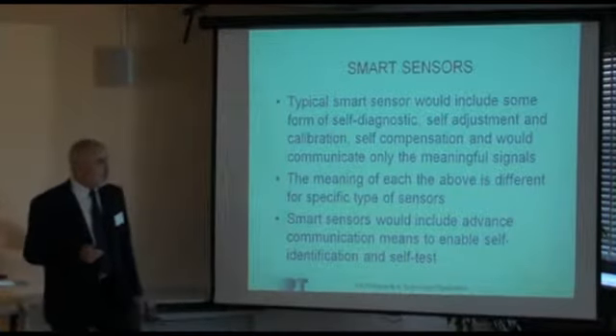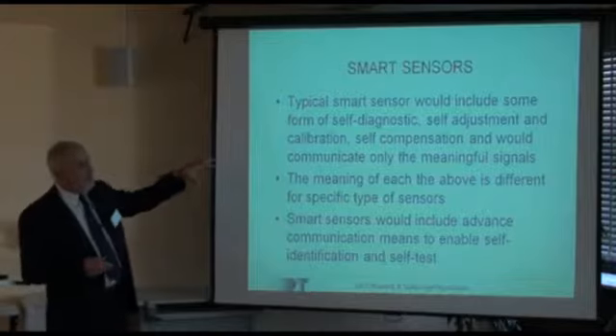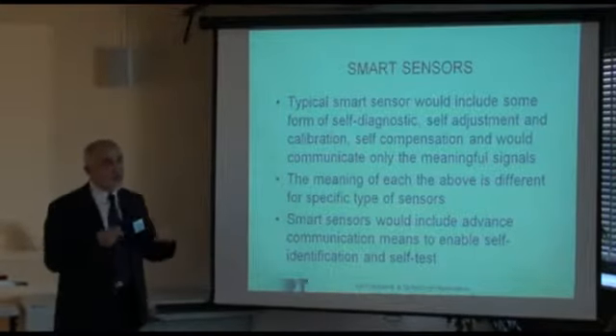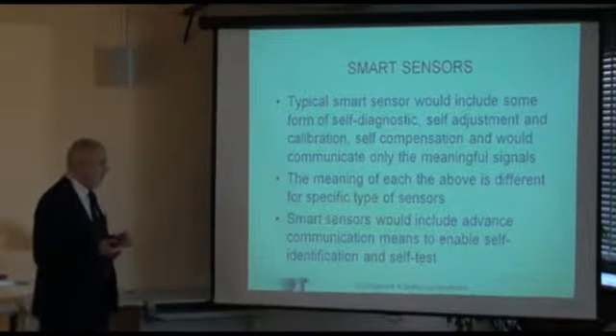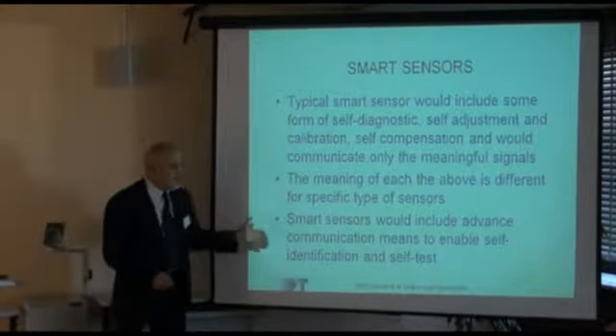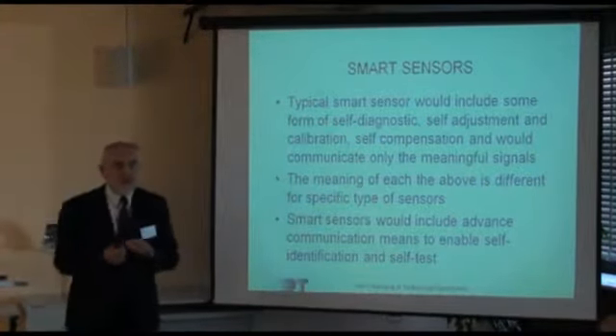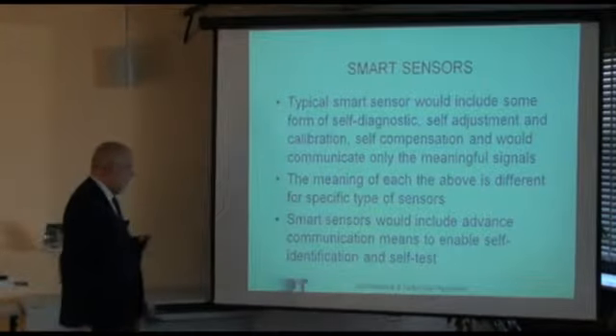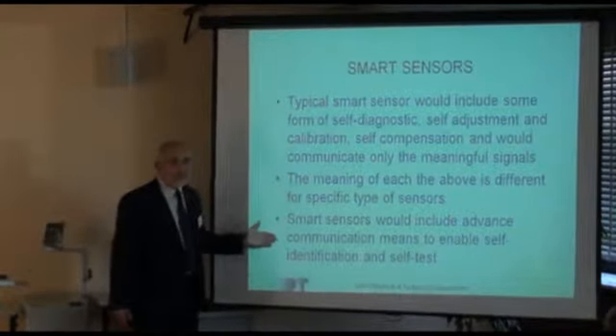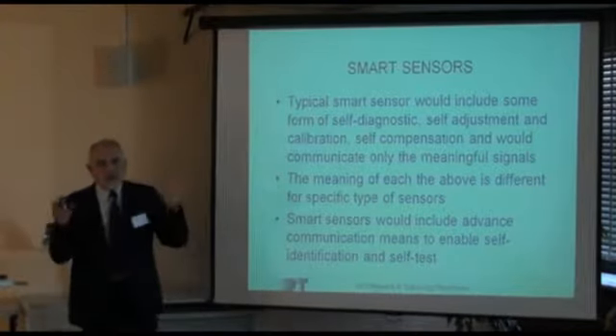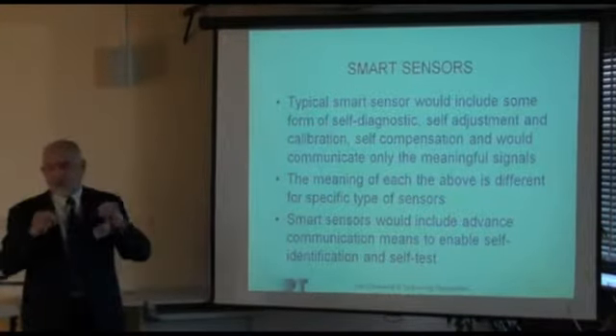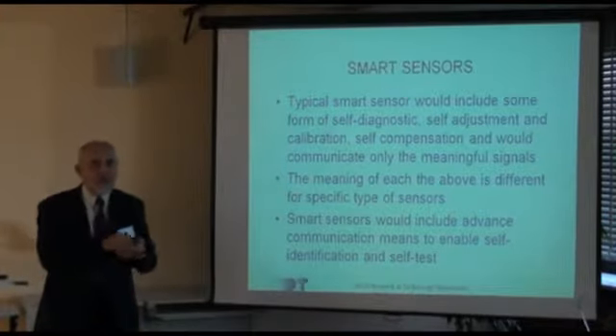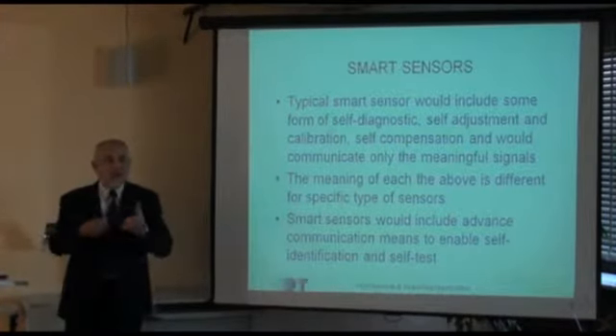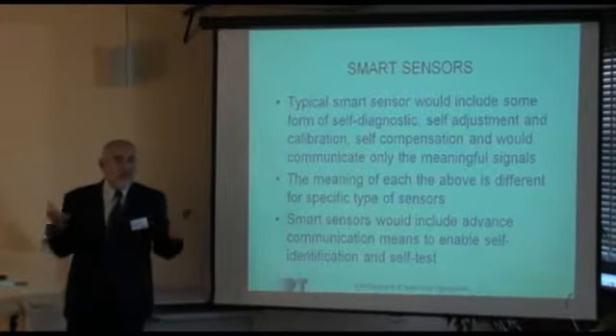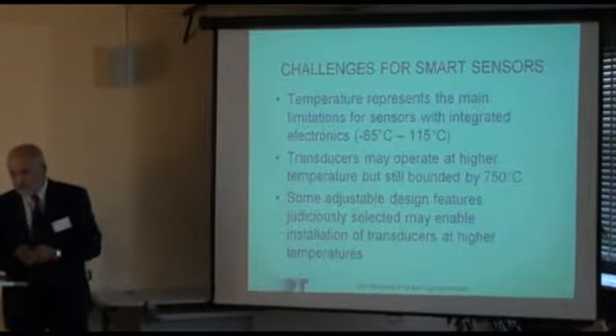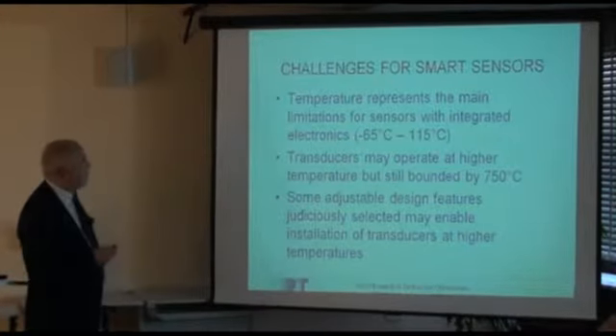The meaning of each of the above—self-diagnostic, self-adjustment, calibration—may be different for different classes of sensors. A smart sensor might also include advanced communication means, protocols that would enable self-communication and self-test. The constant of the sensor is transmitted automatically because it's retained somewhere in memory, which facilitates fast and immediate interchangeability. So, challenges for smart sensors.